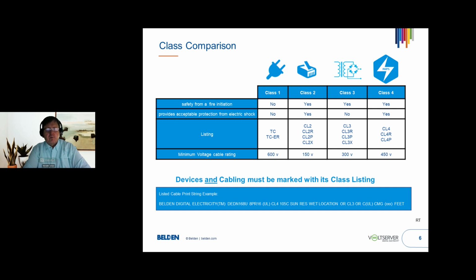The other important thing I want to point out with the cabling is that the devices and the cabling must be marked with the class listing. I gave an example of what that print string would look like on a Class 4 cable. You can see here Belden Digital Electricity, and here's our part number. It's an 8-pair 16 gauge. It's been certified by UL as CL4.